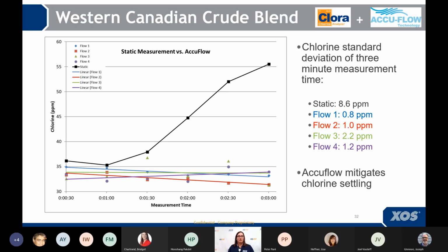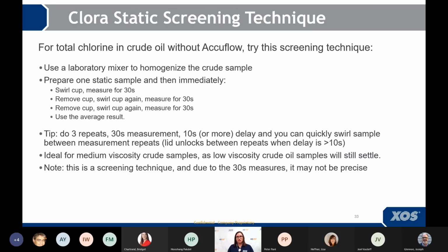you don't have AccuFlow. So we do have a static screening technique. There is an oil major that actually uses this technique as their way of measuring chlorine. And what you do is essentially you're going to take a static sample cup, and use a shorter measurement time with repeats. And you essentially shake the sample or swirl it in between repeats so the chlorine doesn't have a chance to settle. Do note that, for starters, the chlorine is not stable, and so it's still trying to settle. And also that these are a 30-second measurement. So this is why we call it a screening technique, because we do not expect this to be precise. This is just to give you an idea of what's actually in that sample.